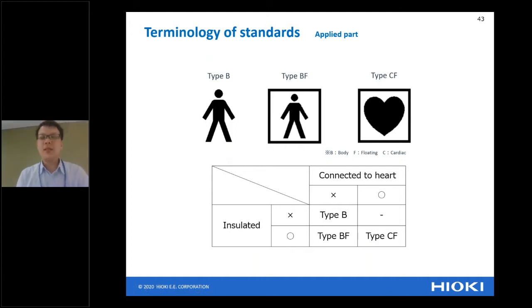So this picture shows the applied parts for medical devices. There are three types: type B, type BF, and type CF. What's the difference? Please check here: connected to the heart and insulated. That's why we call it type CF. Type CF medical equipment needs a very, very high class of safety, like this.